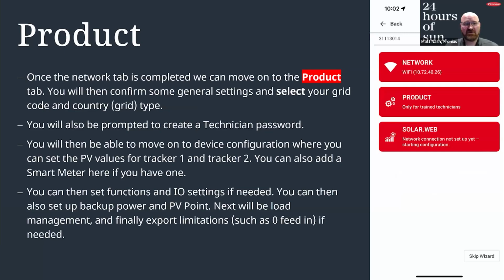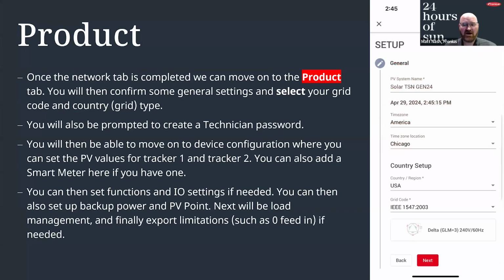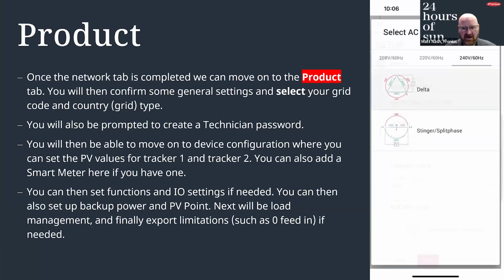Next thing you're going to do is you're going to go into the product tab. This is where you're going to set up your grid code. It's going to ask you if everything's correct with the time zone and things like that. So you would be able to select what type of system it is, whether it be a delta without a neutral or split phase. It'll actually sense what voltage is going in, so you don't have to adjust anything here. You just need to select with or without a neutral.